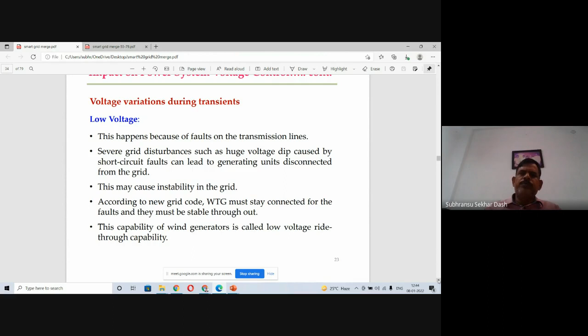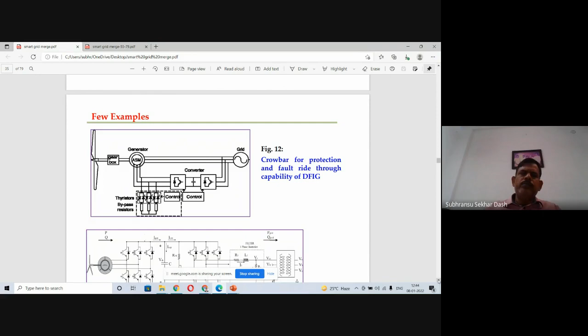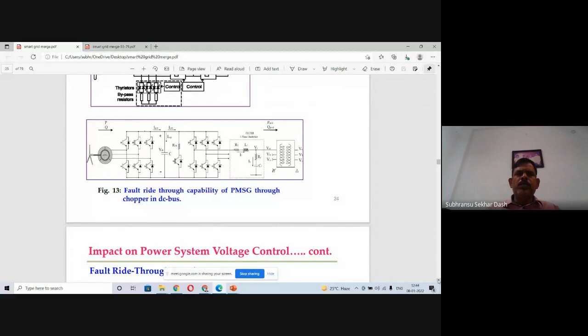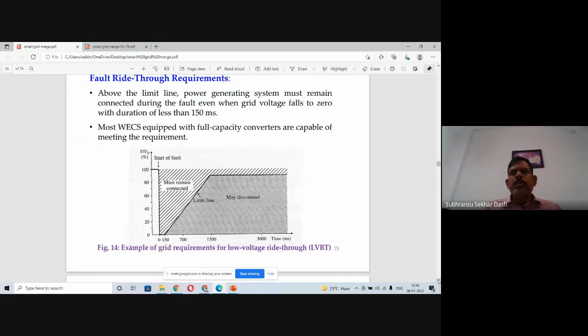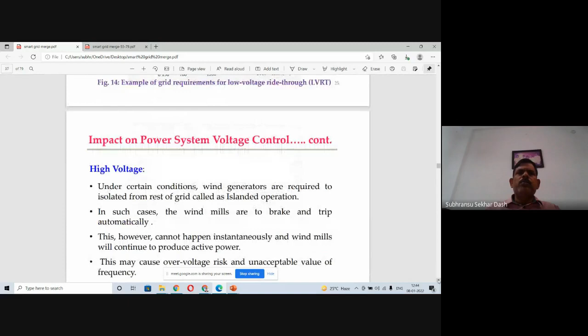Here a crowbar for protection and the fault ride-through capability of doubly fed induction generators is given. Fault ride-through capability of PMSG, permanent magnet synchronous generator, through a chopper in the DC bus. Impact on power system voltage control. Fault ride-through requirements are given. It may disconnect, or it must remain connected, as given in the diagrams. Impact on power system voltage and high voltage.